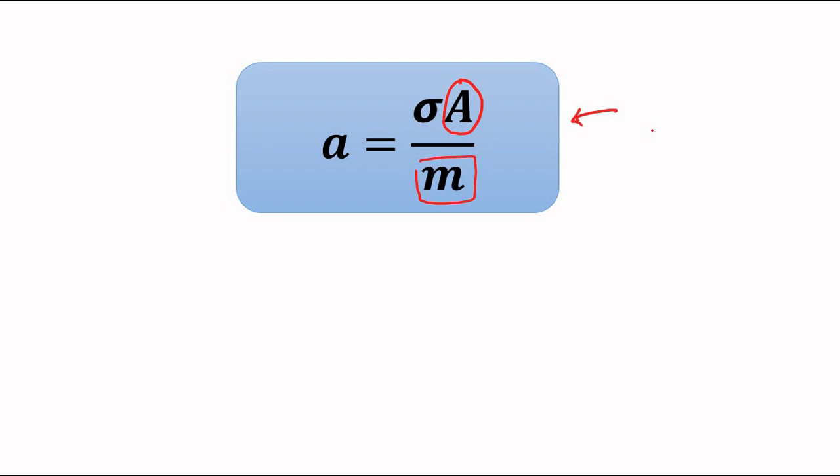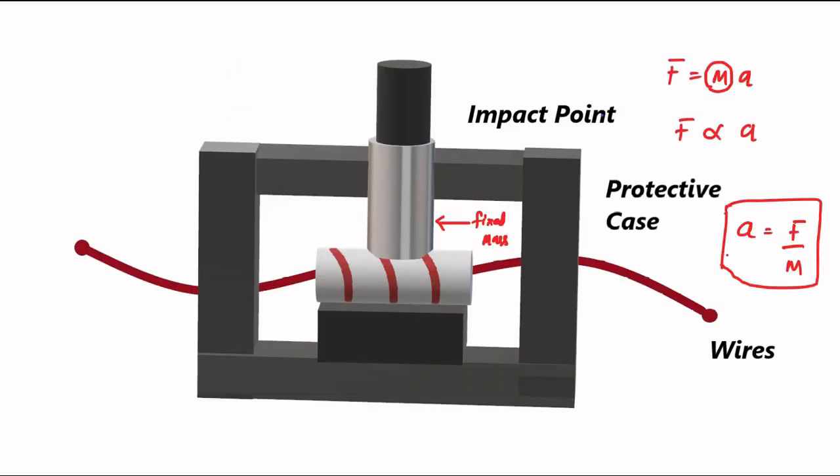Okay, so the calibration has to be done in terms of acceleration and stress in case of a magnetostrictive pressure sensor used as an acceleration sensor, or in terms of acceleration and force when it is the force transducer which is used for acceleration measurement. The basic working principle of the sensor is the same.